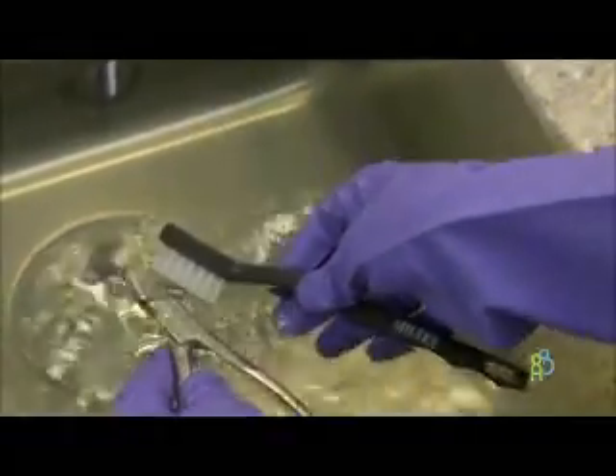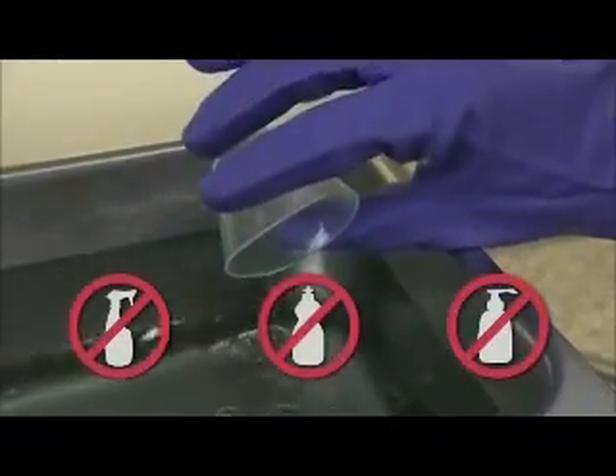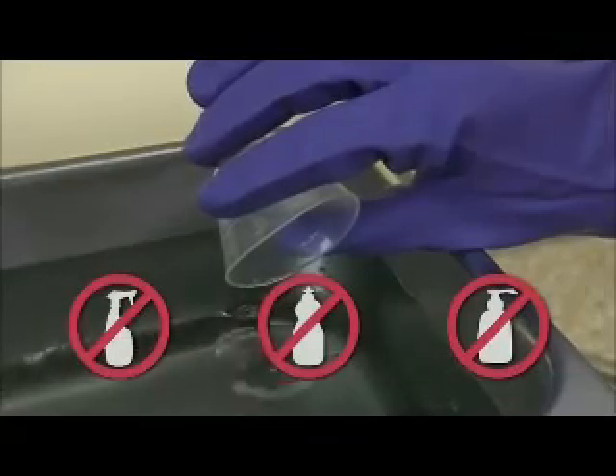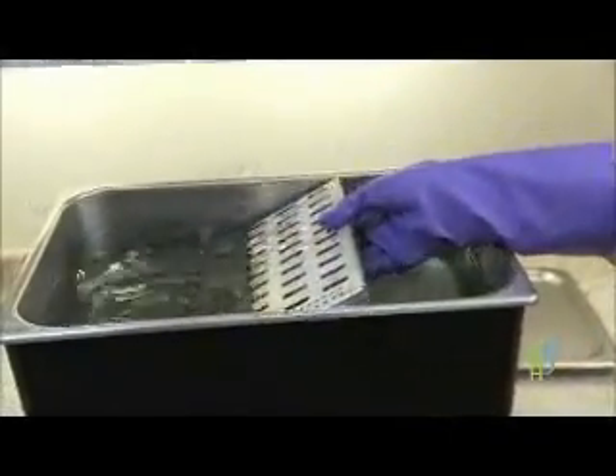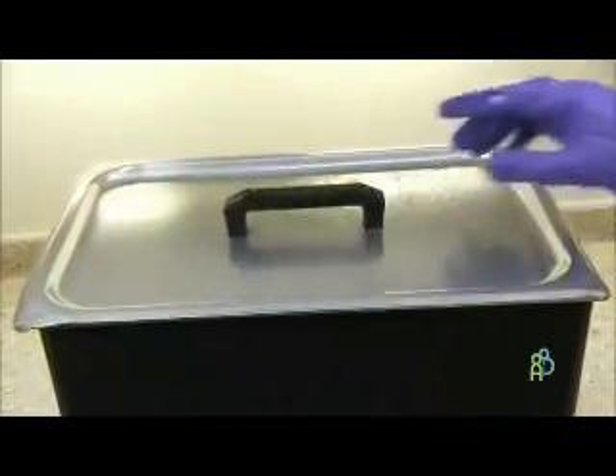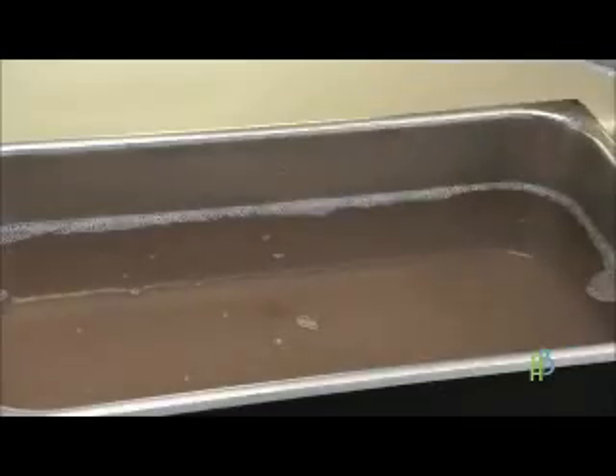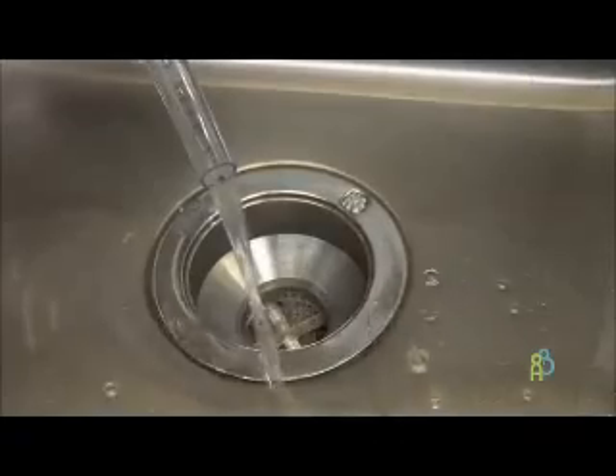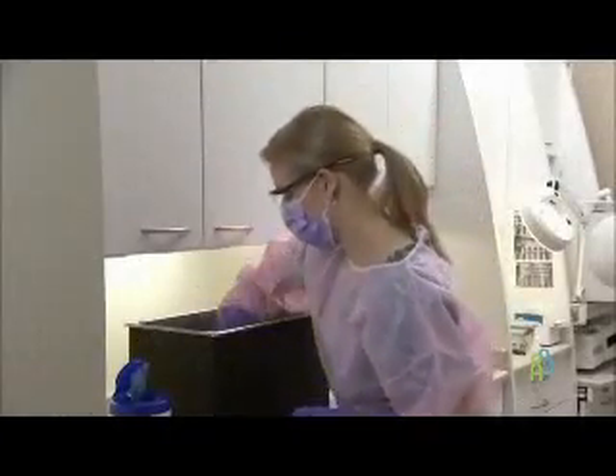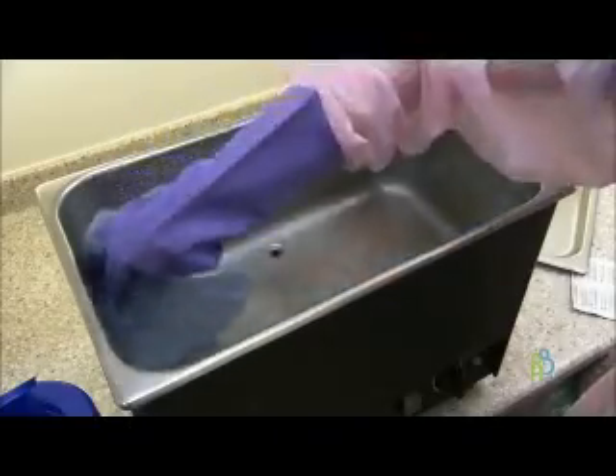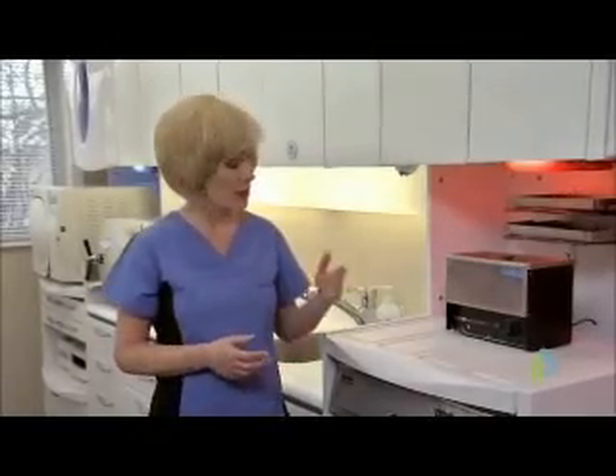Visible soil shall be removed prior to devices being placed in an ultrasonic cleaner, as heavy soiling interferes with the ultrasonic cavitation process. Household cleaners, dish soaps, or hand cleaners are not acceptable as cleaning agents for dental devices. Ensure devices are completely immersed in the cleaning solution, and ensure that the lid is closed to prevent splashing and aerosols. The cleaning solution in an ultrasonic cleaner must be replaced daily or more frequently if the solution becomes visibly soiled or if the manufacturer's instructions specify more frequent changes. Soiled instruments must never be stacked or soaked in the ultrasonic cleaner.